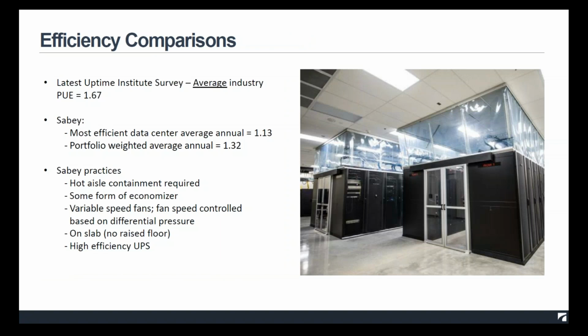So in the latest Uptime Institute survey, the respondents indicated the average industry PUE is 1.67, and that's a little bit higher than the 2017 results. But generally speaking, over the years, the PUE has been going down. I think most people on the call may know what this is, but just in case, PUE is power utilization effectiveness, and essentially it's a measure of the energy overhead. So it's the total energy used by the data center facility divided by the amount of energy that's used by the IT equipment. Ideally, you want that to be as close to 1 as possible. A PUE of 1 would be perfect. It would mean all of the energy going into the facility is actually being used by the IT equipment.